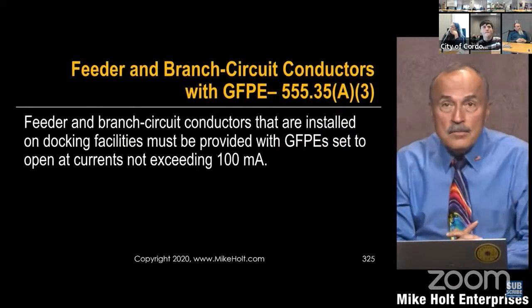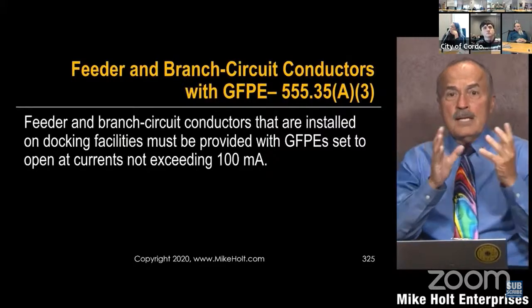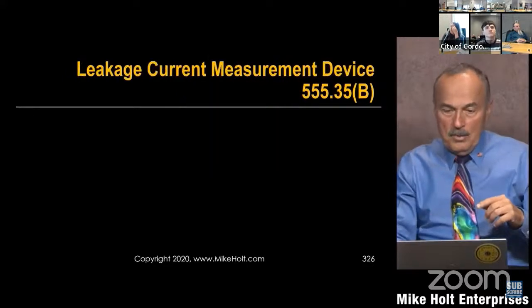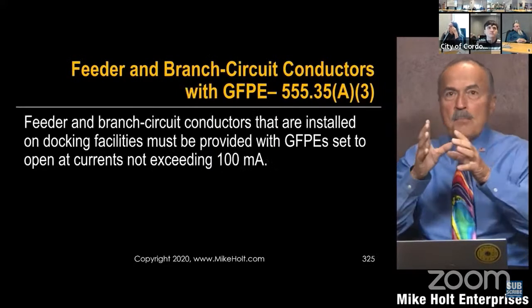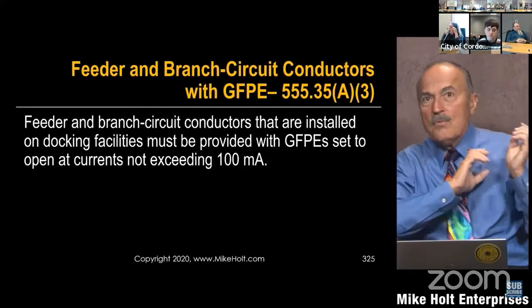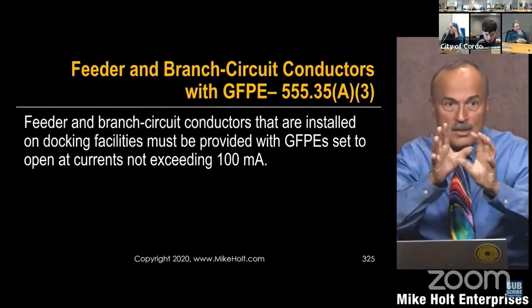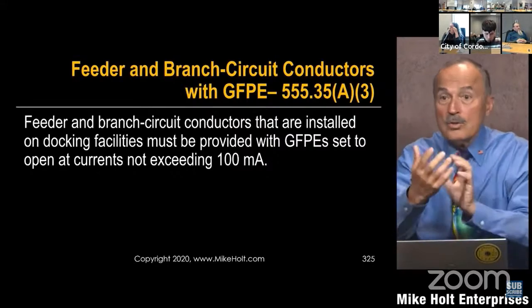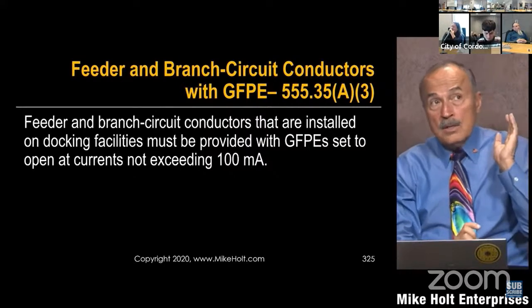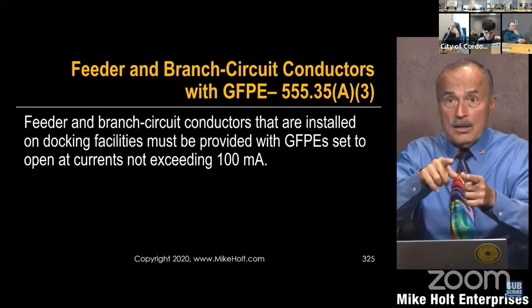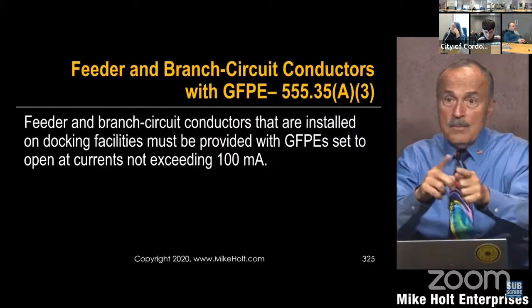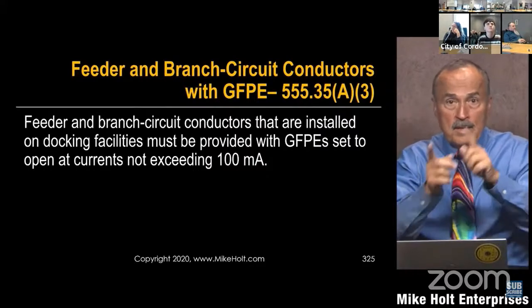Okay. Now the feeder. Remember we talked about that pedestal? Probably need to get a picture of a pedestal, Brian. I don't have a picture here. We have a pedestal, and I'm running a 200 amp feeder out to that pedestal that can supply four 100 amp feeders. Well, the shore power breaker for the receptacle is set at 30 milliamperes, but the feeder that runs out to the shore power, that's set at 100 milliamps.